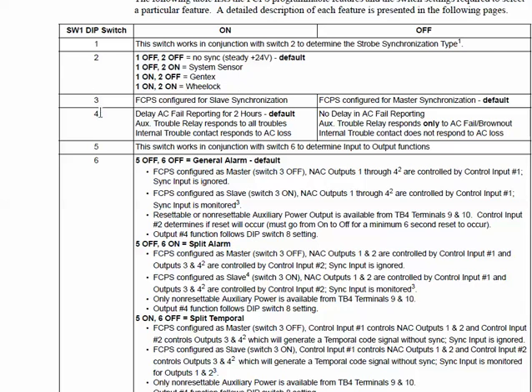First of all, look at number 3. If DIP switch 3 is set to on, then the FCPS is configured for slave synchronization. So that means it's going to follow your fire alarm panel, or whatever your trigger is.